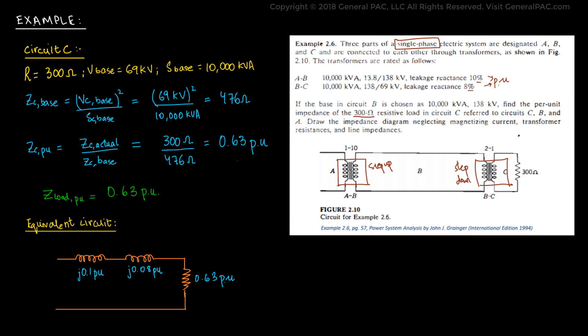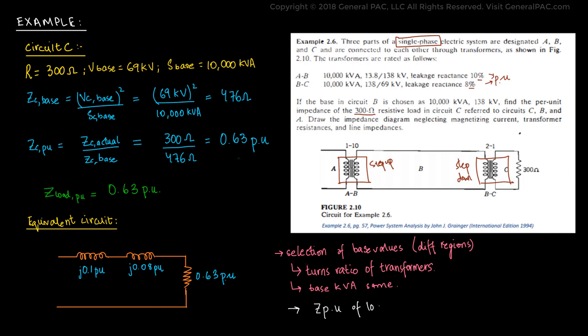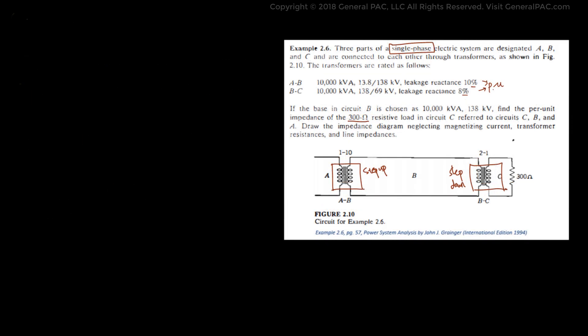Despite already solving part of the answer, we will go through and show the advantages of per unit systems. Because the selection of the base in various regions is determined by the turns ratio of the transformer, and because the base kVA is the same in all regions, the per unit impedance of the load transferred to any region of the system will be exactly the same. This will be illustrated in the remaining parts of this tutorial. We know the per unit impedance in circuit B will equal that in circuit C, i.e., 0.63 per unit, as described in Part 2c.